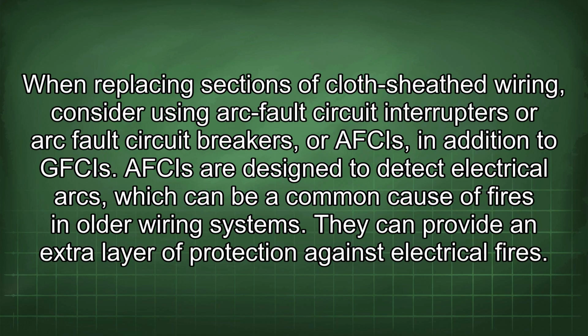When replacing sections of cloth-sheathed wiring, consider using arc fault circuit interrupters or arc fault circuit breakers, or AFCIs, in addition to GFCIs. AFCIs are designed to detect electrical arcs, which can be a common cause of fires in older wiring systems. They can provide an extra layer of protection against electrical fires.